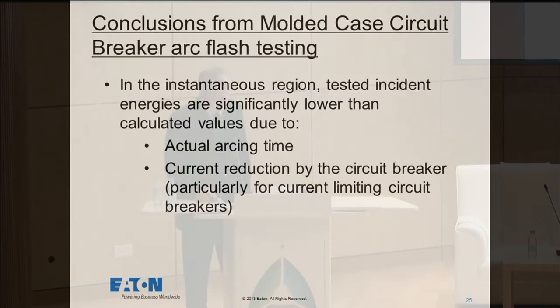And so why is that? The reason we know that happens is because molded case circuit breakers, when they operate instantaneously, which means they're above the threshold of their pickups, operate very quickly. And when they operate very quickly, their contacts begin to separate. As soon as their contacts begin to separate, there's an arc inside the breaker. Inside the breaker are arc chutes to break that arc up so that it can interrupt it and stop the flow of current.